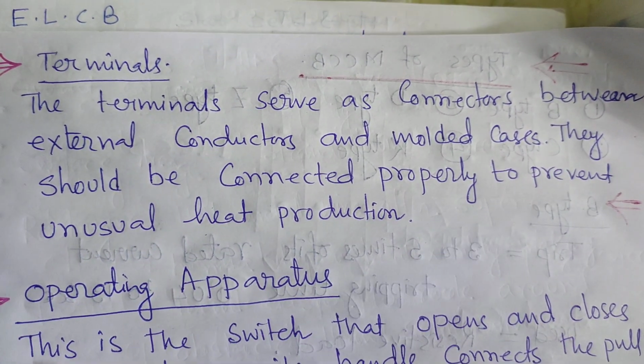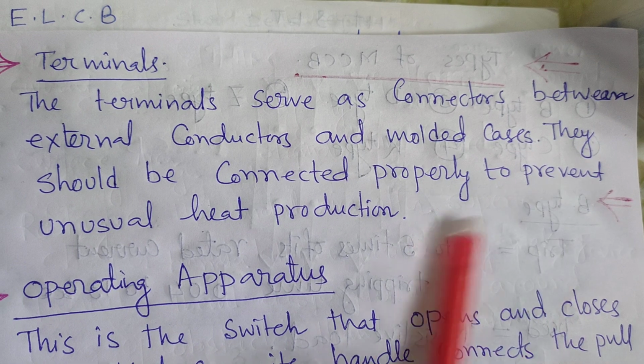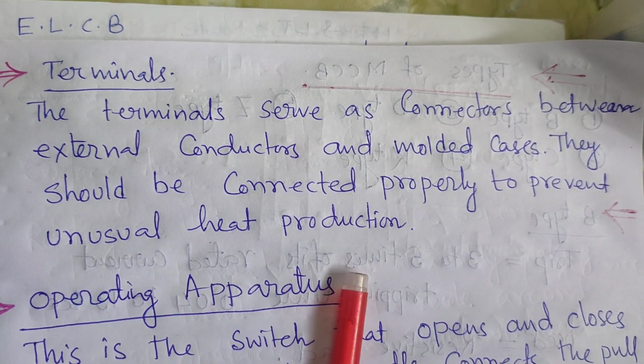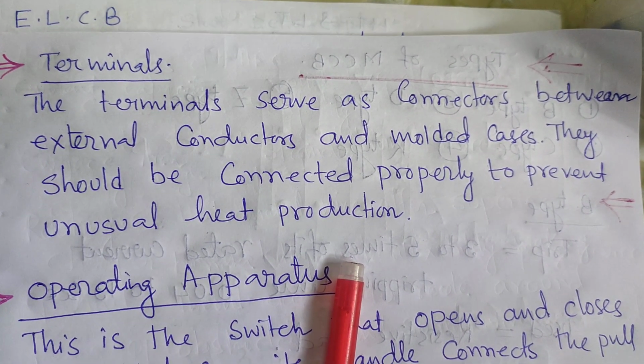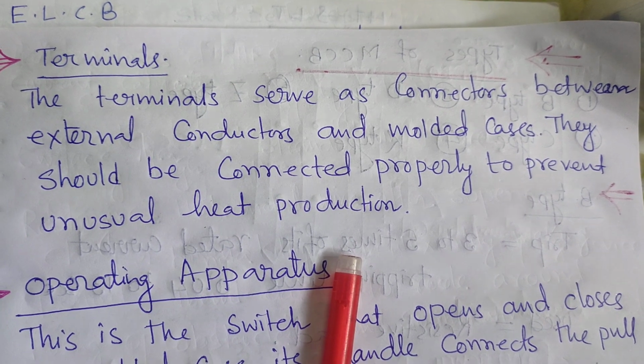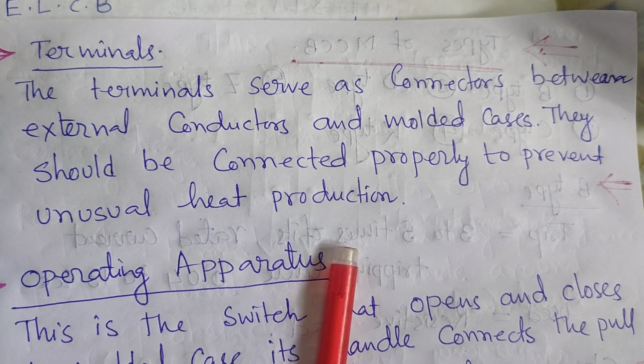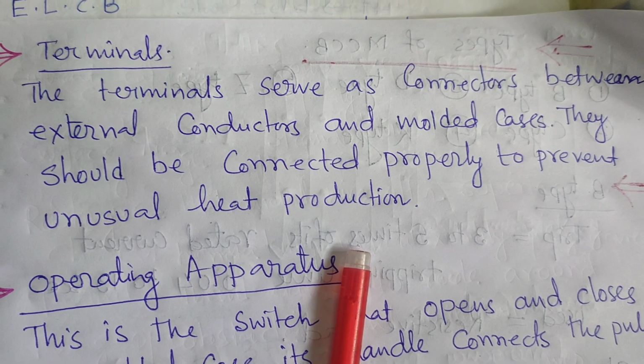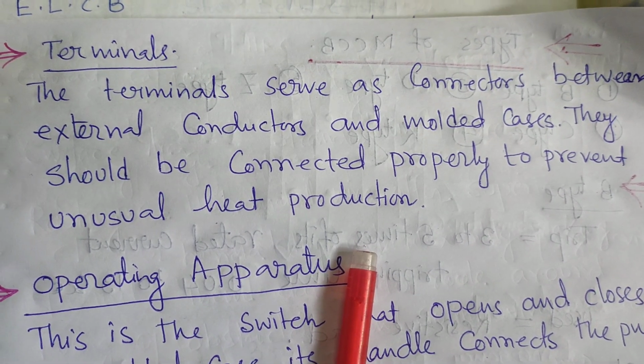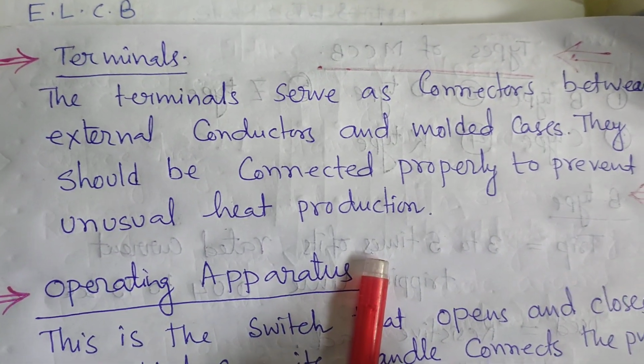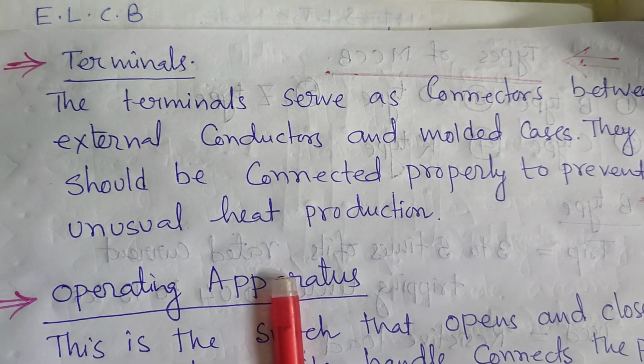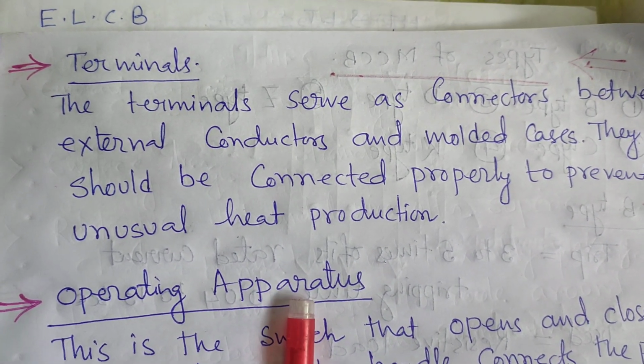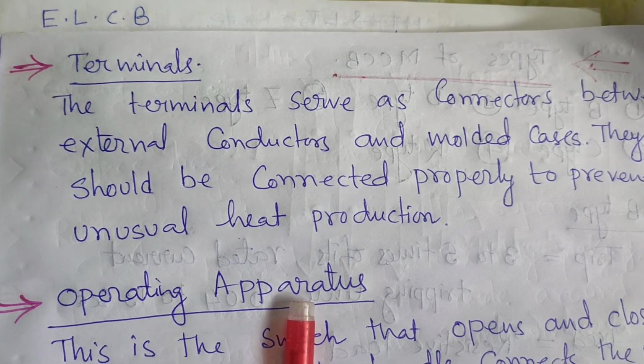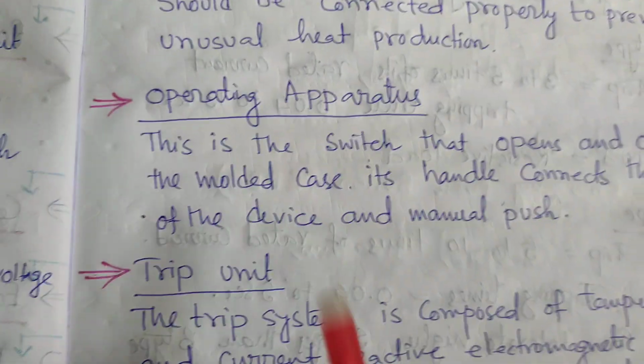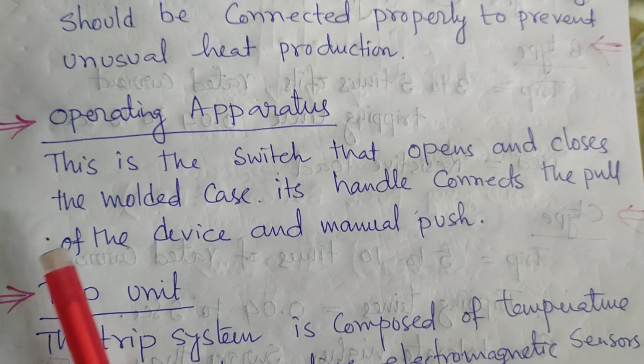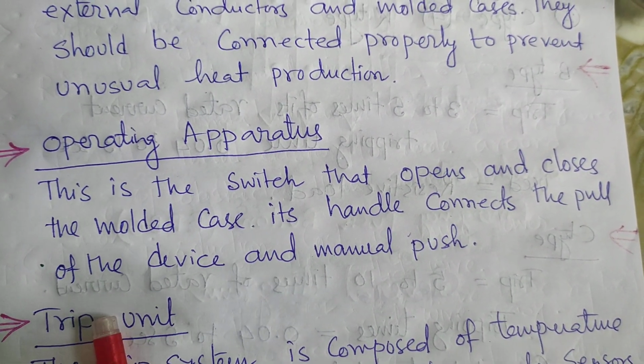The external conductor and molded case should be connected properly to prevent unusual heat production. You should check the tightness of the connectors, because if the connectors are tight, then no heat will be generated and no arcing will be there. If it is loose, the loose contact can produce heat, and that heat can burn or melt the connectors also. Operating apparatus. This is the switch that opens and closes.